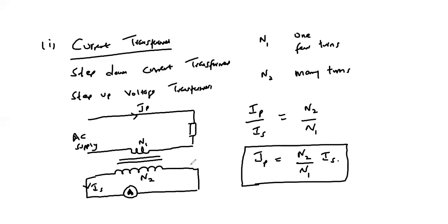It is important to notice that the secondary winding of the current transformer must never be left open. If left open, the current in the secondary becomes zero, and since this current normally opposes the primary ampere-turns, there is no counter magnetomotive force. The unopposed primary magnetomotive force produces high flux in the core, resulting in excessive core losses and overheating of the core beyond safe limits.